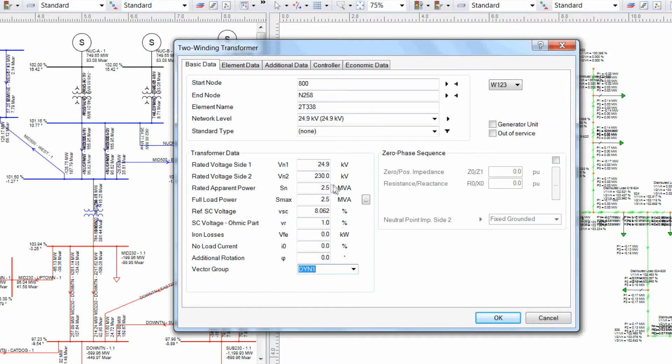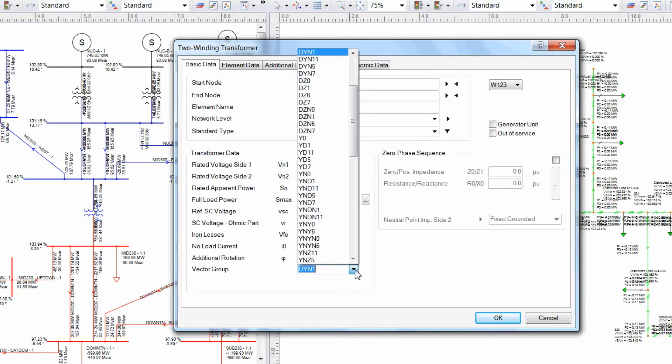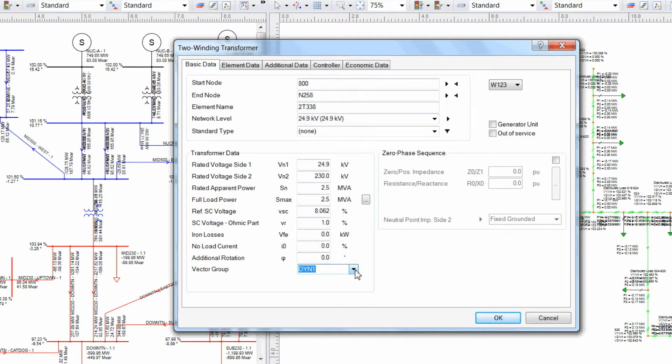Ensure that the primary and secondary voltage on the transformer is set up correctly, and define the vector group for the transformer. The vector group must have a neutral connection for the unbalanced currents to flow.